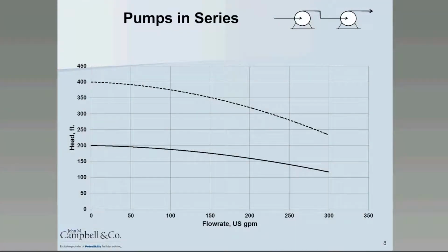So looking at pumps in series, what I've done here is I've drawn onto this chart from that vendor pump curve that we had previously, the pump curve for a single pump.